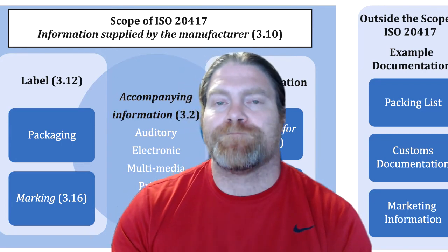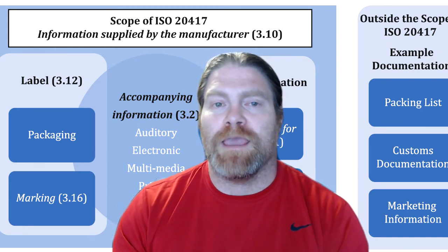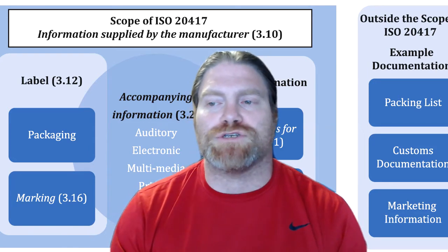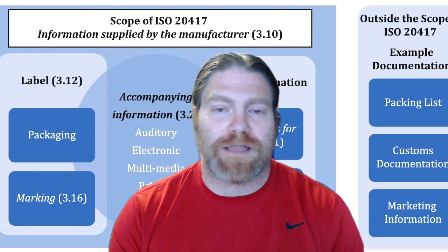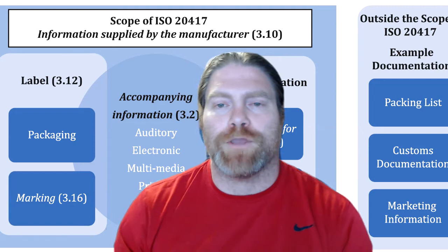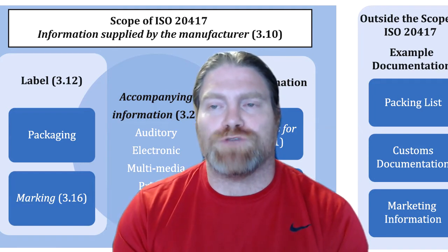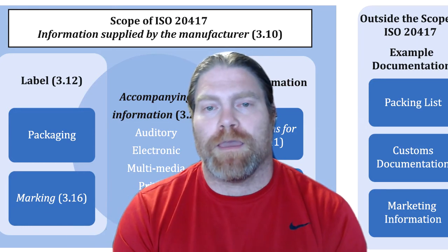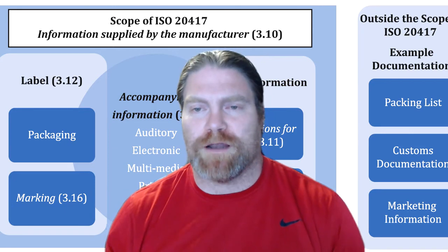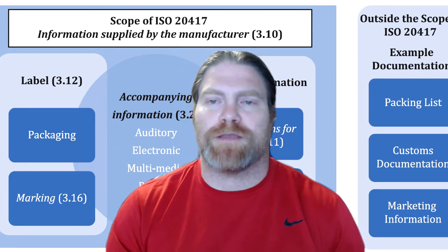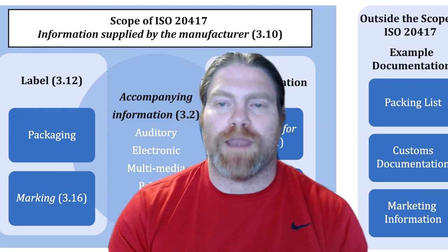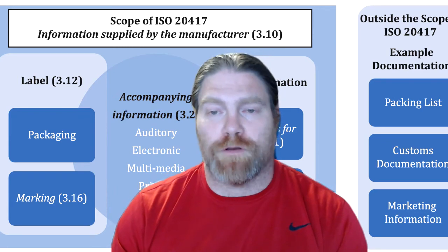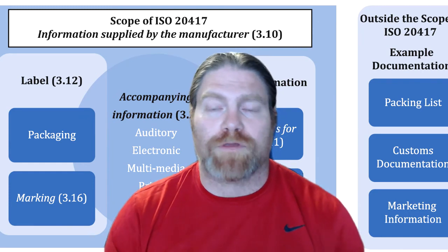You need to make sure that you have translations for each member state in one of the recognized languages for that member state. If they recognize four different languages, you need to provide it in one of those languages — or potentially all four. Some member states require multiple languages, some only one. But you have to cover the languages required by each member state if you're going to ship there. And you're going to have to make those available on your website for download. Companies in the past were saying they'd translate on demand using Google Translate — that's not going to work. You need an accurate translation with a proper process, done before you make your product available in those markets. You actually have to show evidence of that to your notified body, and it can be requested by your authorized representative or the competent authority as well.